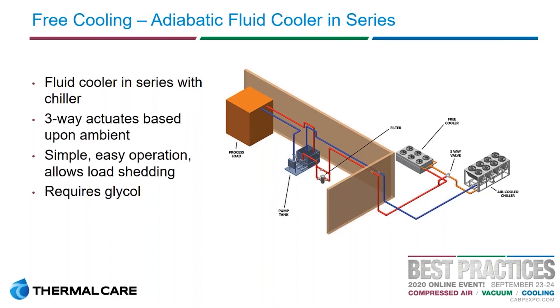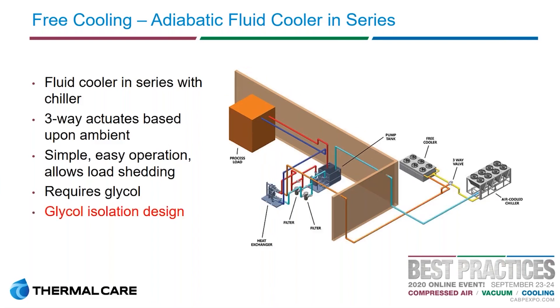One thing to consider is that, just like a packaged air-cooled chiller sitting outside, you are now sending water outdoors. There exists a scenario where that water could potentially be trapped outside in the winter and could freeze. So this type of system design does require a glycol mixture. To address that, we would use a heat exchanger, which is a very similar setup to the previous slide but with a heat exchanger added to isolate a 100% pure water loop from a glycol mixture loop.